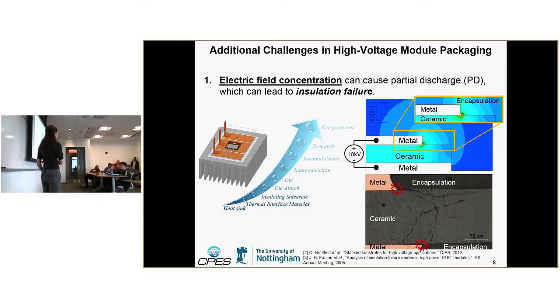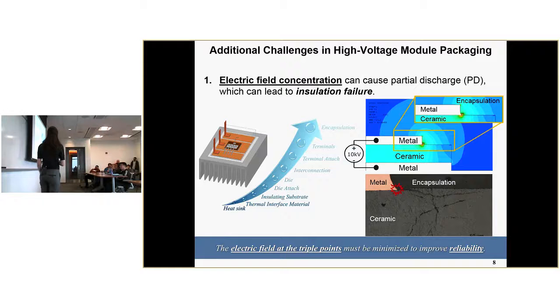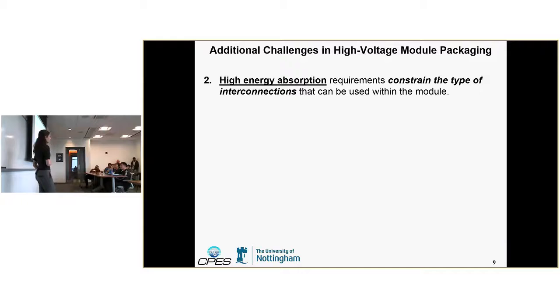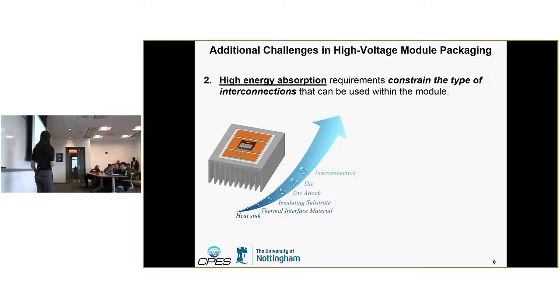So then that completely destroys the isolation from your heatsink, and now your module and your whole system could be damaged. So it's really essential that in these high voltage modules, especially if you want to achieve high density, you need to make sure that the electric field at these triple points is well controlled. Another thing for higher power applications is high energy absorption. So when you have a fault, you need to make sure that you're able to handle higher amounts of energy. And this is primarily a concern with the interconnection.